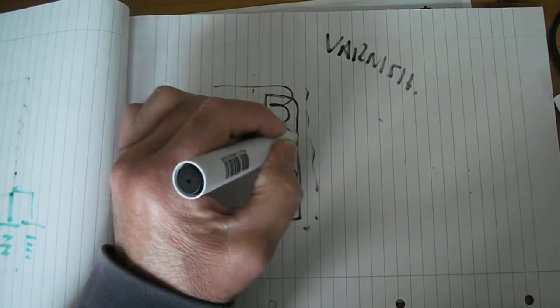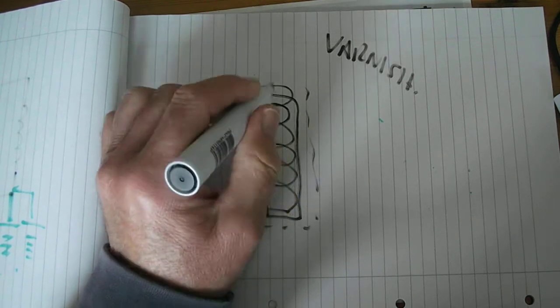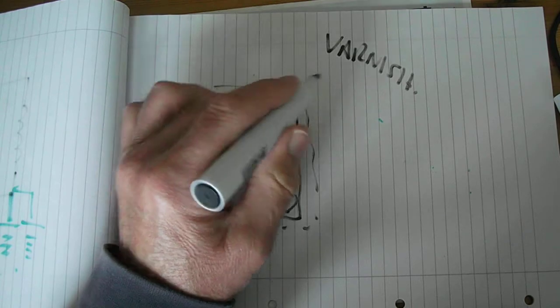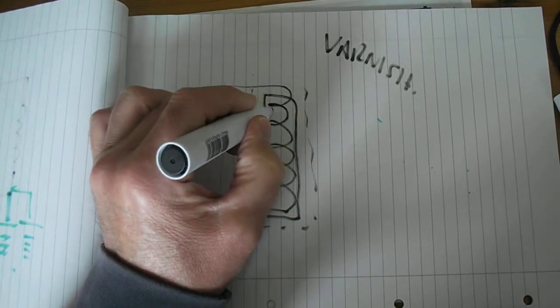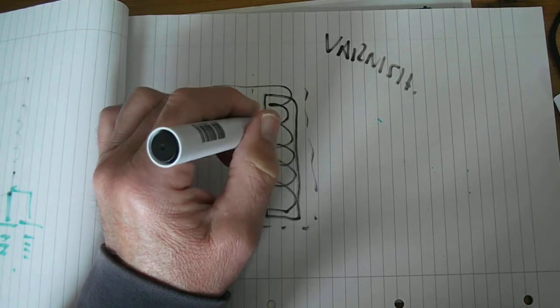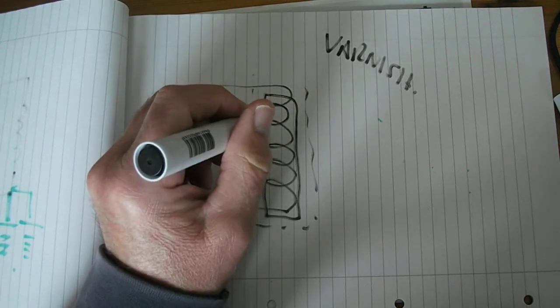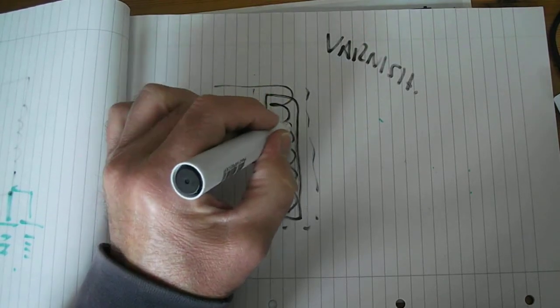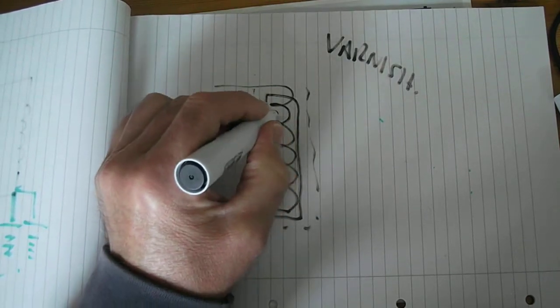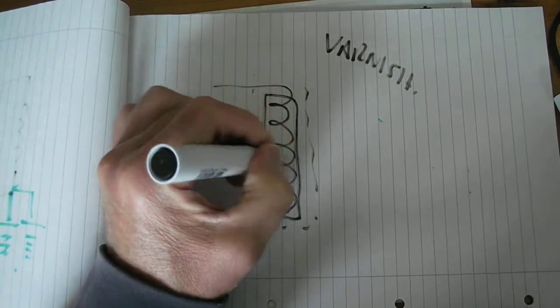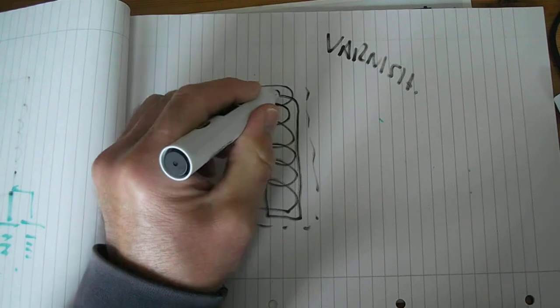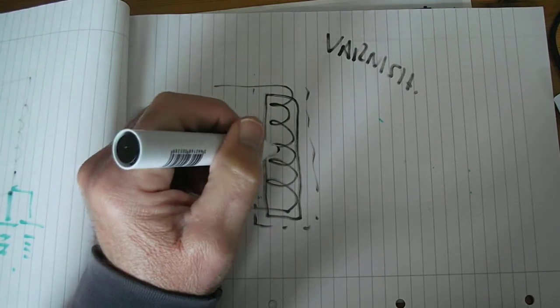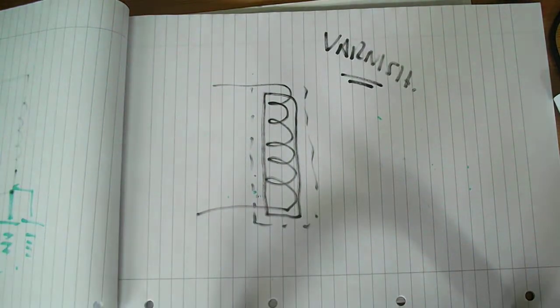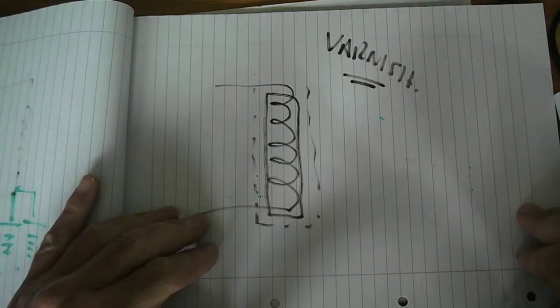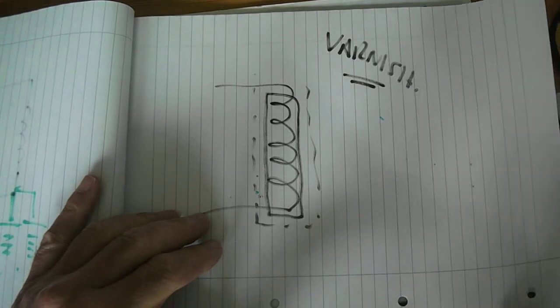You could use rubber, or you could use PVC, but it'd be too thick. The thinner the varnish is, the more tightly packed you can have the windings, and they're very close together. Because the winding itself must be insulated, because if it wasn't insulated, it would just be a solid lump of copper, and it wouldn't function as a winding. It would just function as a piece of wire going from A to B. So varnish is the preferred insulator on transformers. Okay.